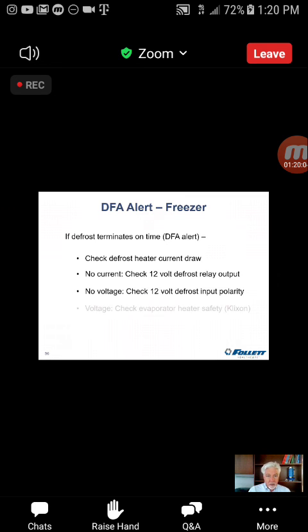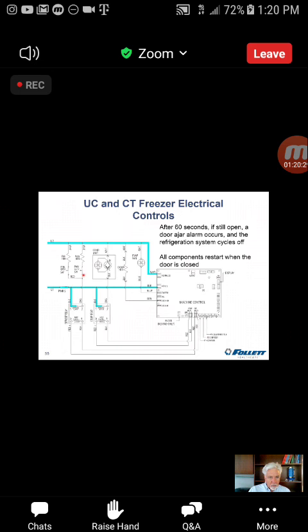If all of that looks good, then let's make sure that we're delivering voltage to the heater. Check the voltage on the contact side, on the contact terminals there. Make sure that we're delivering voltage to the heater. If we are, but we're still not getting current draw, don't forget about that little Klixon, that little safety. Matter of fact, I'm going to back it up to the schematic so I can show you in the schematic where those are located. Here they are, right there. Those are the safeties.